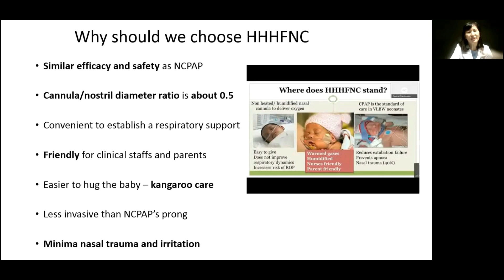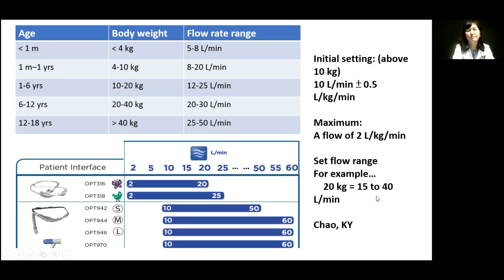The high flow rate is set according to age and body weight. For example, for the initial setting there is a formula. For example, for a 20 kilogram child, the flow rate range is 15 to 40 liters per minute.